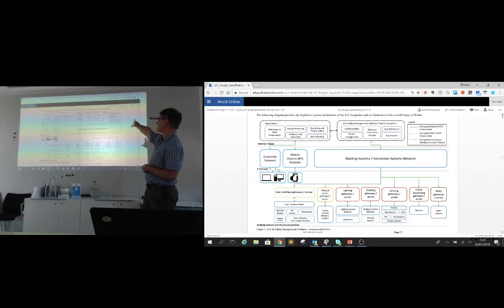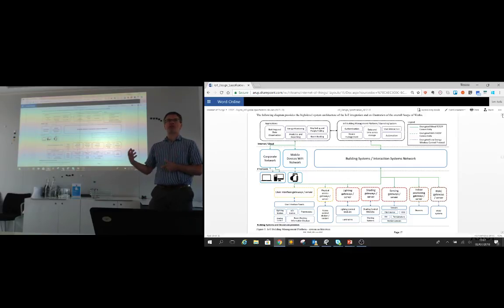And it's on the cloud services in the internet in data centers that are outside the building where our horizontal integration between systems and between buildings takes place, and also crucially between user interface devices like your phone and the building. Because all of those devices have access to the internet, it's much cleaner and much lower cost for us to do integration in the cloud than it is trying to penetrate through firewalls within the building.